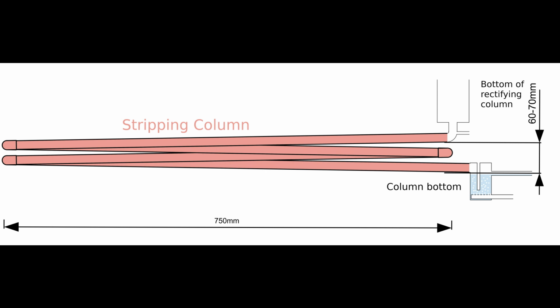And it is simply an insulated tube sloping downwards at a shallow gradient. It is a 3 metre length of 15 mm copper pipe sloping down at a gradient of between 40 and 50 to 1. For convenience and to make it easier to insulate, I cut the pipe into 4 750 mm sections, then make it into a rectangular spiral or zigzag. It's made of 6 90-degree elbows, 3 pieces of copper tube 20 mm long and 4 pieces 750 mm long.